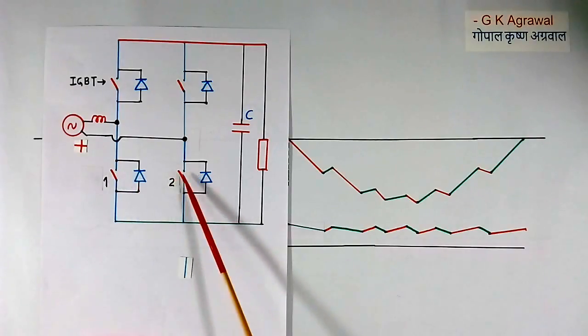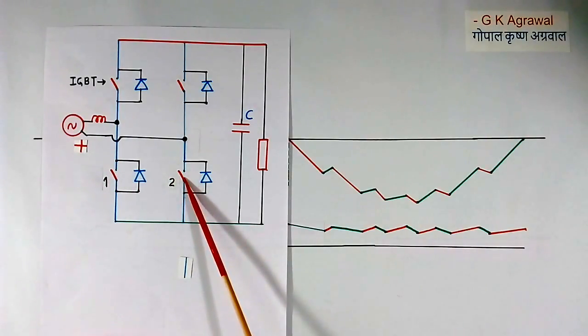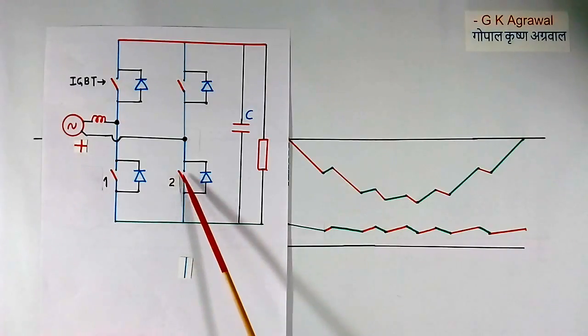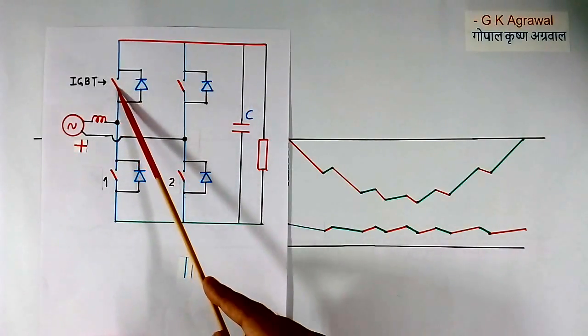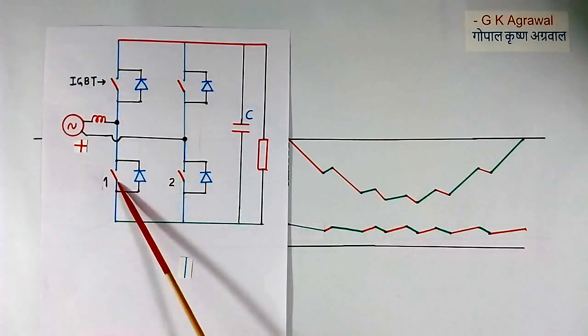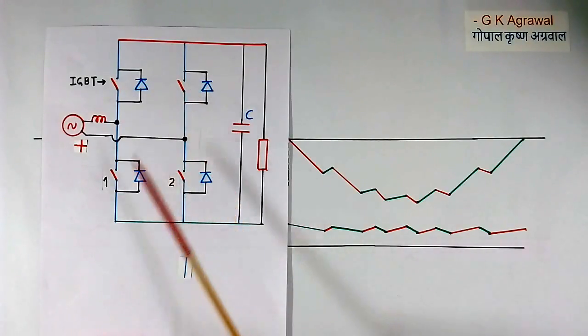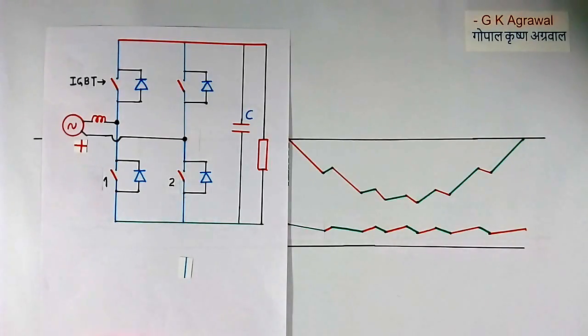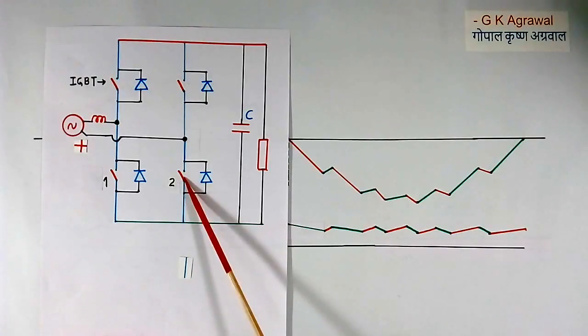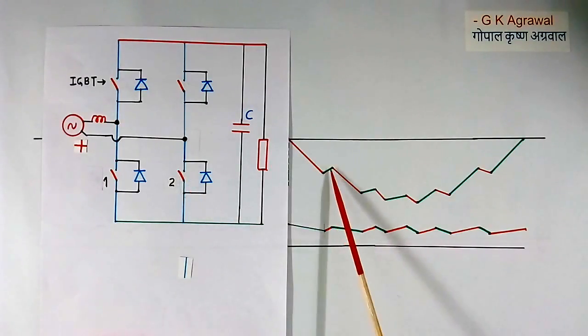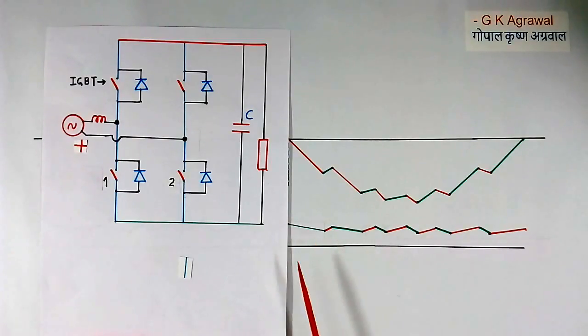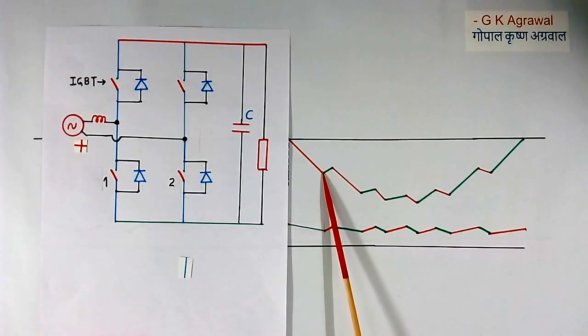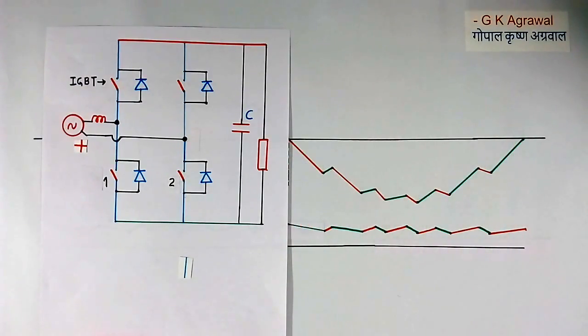So here only 2 IGBTs are sufficient to control the system, but in fact there will be 4 IGBTs. The remaining 2 will either not be used, or sometimes these 2 will be used and sometimes the other 2, or some other combination, such that heating is less. By making this IGBT switch on and off at very high frequency, we can bring this ripple very low. We can select the switching on and off time as we want, so we can shape the current waveform and control the power factor as well.